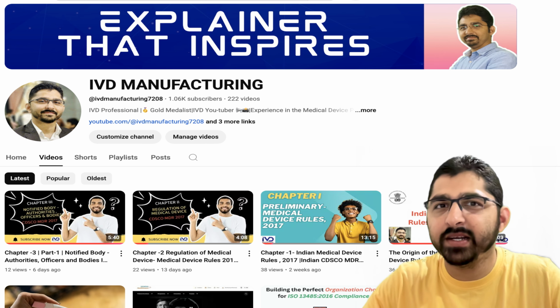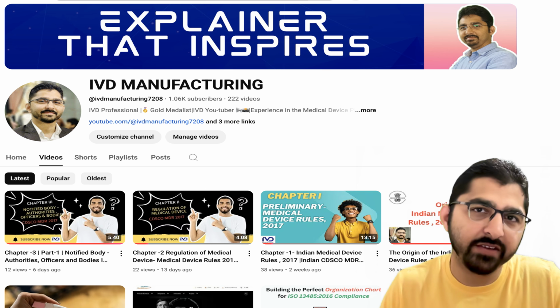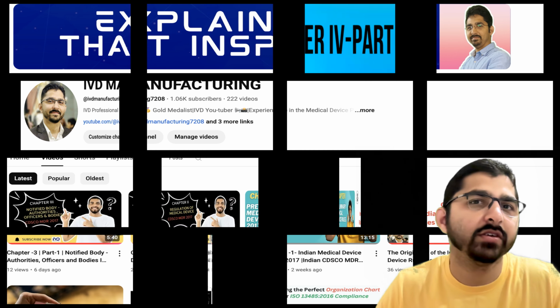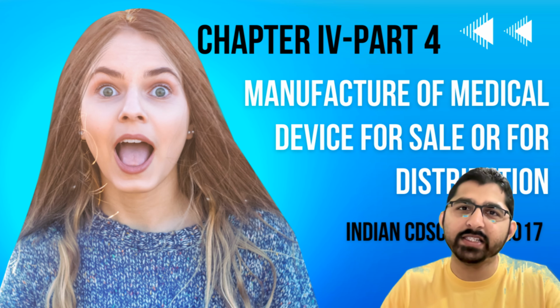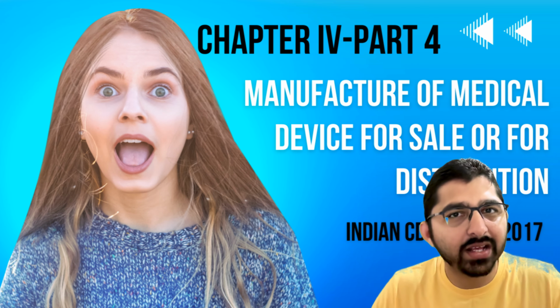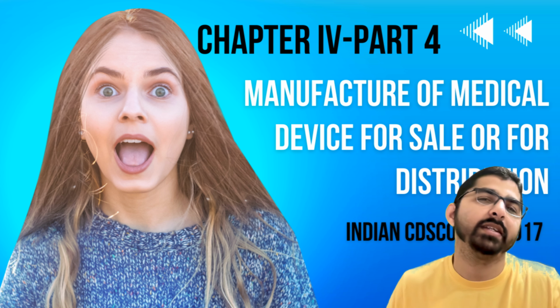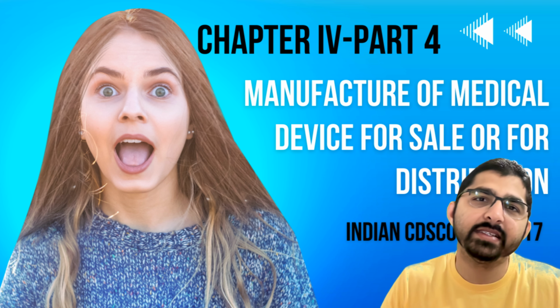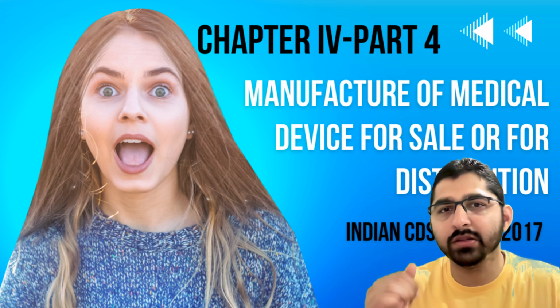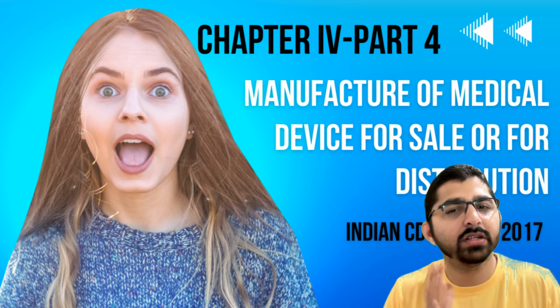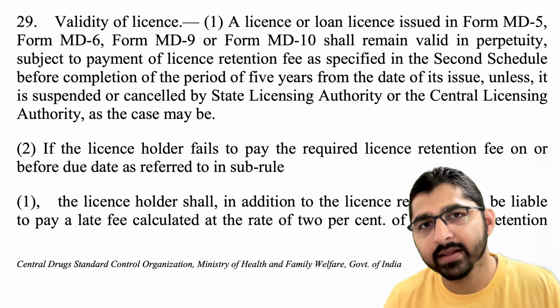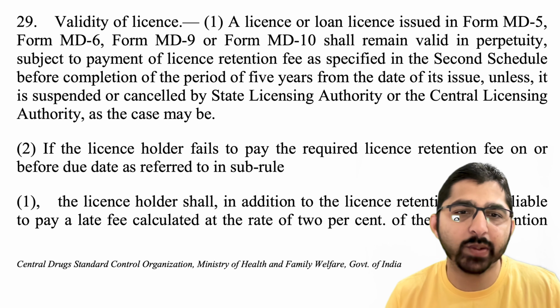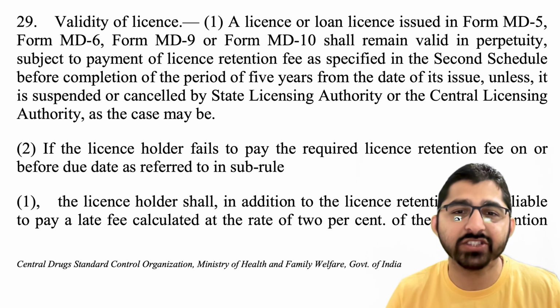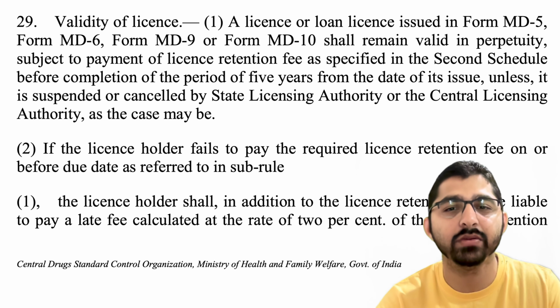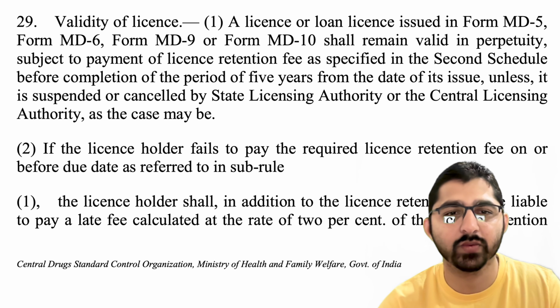So today we'll be discussing chapter 4 of Indian CDSCO MDR 2017, where we'll be talking about the validity of a license once issued by the CDSCO. When I say license, I mean a manufacturing license or the loan license. A license or loan license issued in Form MD5, 6, 9 and 10 shall remain valid in perpetuity subject to the payment of license retention fee as specified in the second schedule of Indian CDSCO MDR 2017.